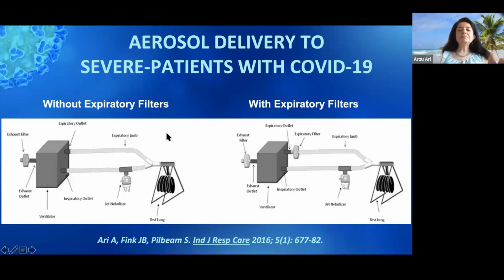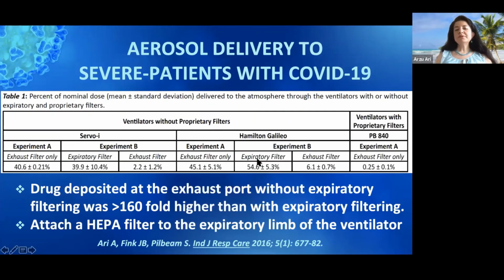So we developed a lung model, an experimental lung model, in which we didn't have any expiratory filters. And at that time, that was the standard of practice in many hospitals. They didn't think they needed an expiratory filter on the expiratory outlet of the ventilator. And then we measured all the aerosols coming through the ventilator at the end of each treatment. And then we repeated the same testing with the same ventilator, with the same conditions, using an expiratory filter on the expiratory outlet. And we again collected all the aerosols during treatment at the exhaust filter placed right here. We tested several different ventilators that were available in our research laboratory at that time.